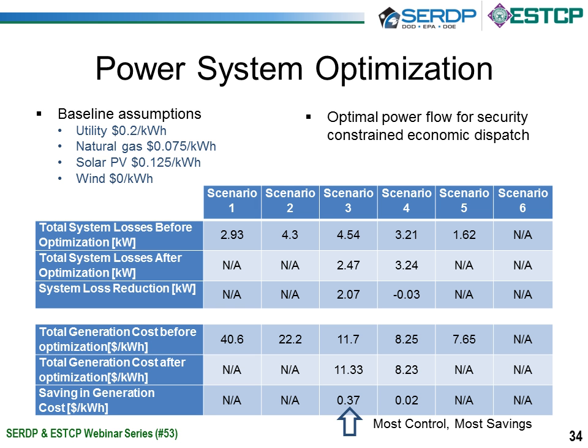The second set begins to cross over between the power modeling side and the economic value of the system. This is a capability we refer to as power system optimization, more commonly known as optimal power flow. It's basically the idea of what is the most economic operation of the system based on variables such as the cost of the energy being used, as well as other things that need to be maintained—most importantly, for a military installation, energy surety. So I want to maximize my economic value, but I cannot create a situation where I've potentially lost the ability for the system to operate.